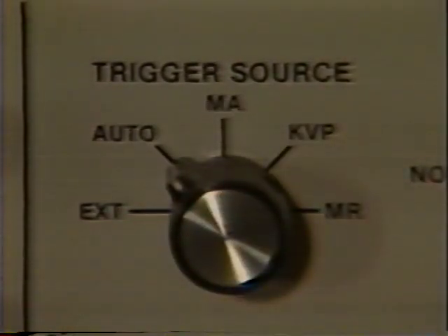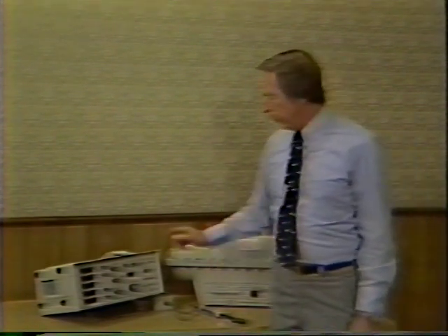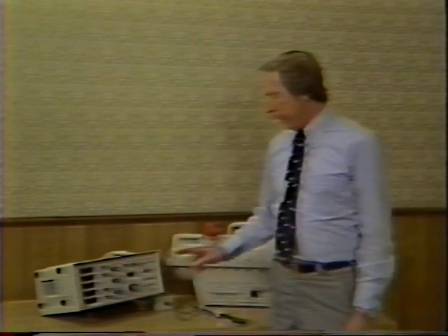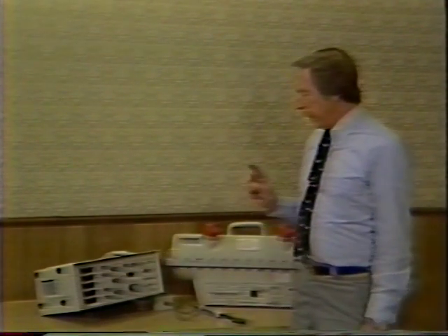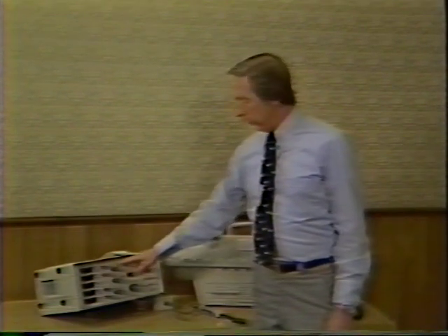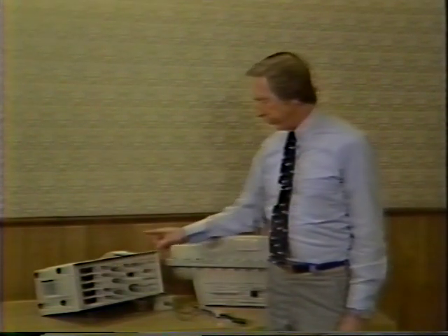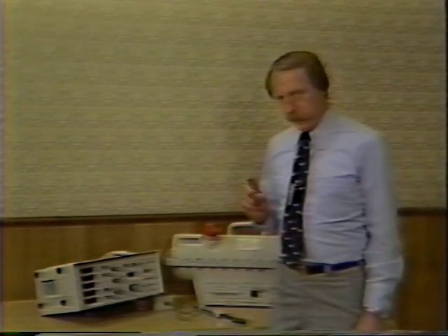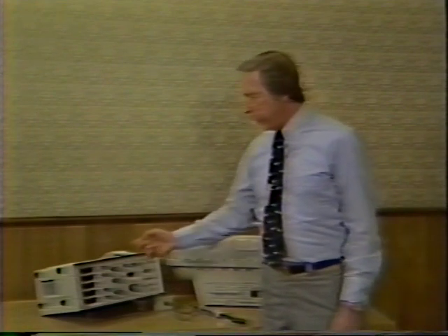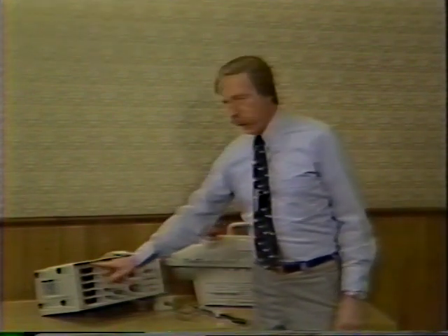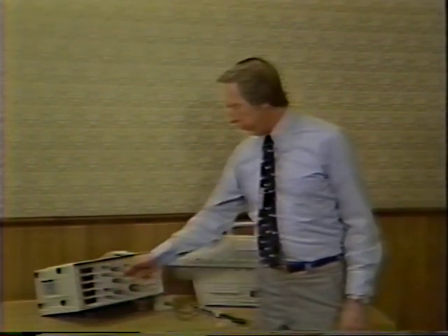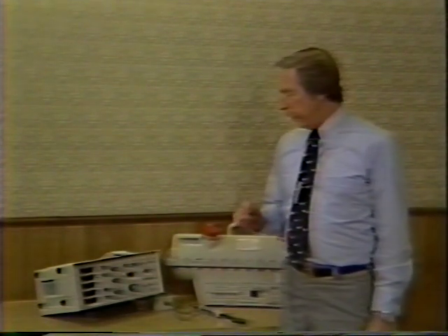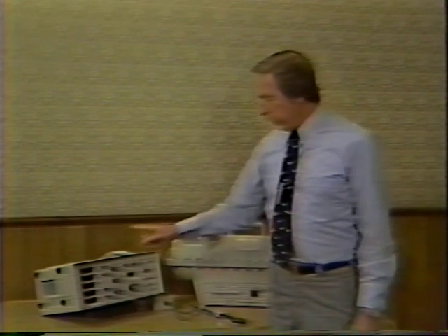One was the auto mode. Let's assume that we have the Dynalyzer in the circuit during a fluoro run. When we step on the foot switch, we trigger this unit and we take our readings. That would only be the case if we did not have the auto mode. In this mode, we're going to trigger the unit every second, such that when we press the foot switch, the unit is being triggered every second. The automatic brightness stabilizer takes over and moves kV or mA. While we're triggering every second, we will constantly have our numbers brought up to date. It's also very useful in the calibration of the filament, in that you can constantly trigger this unit in the auto mode once per second and adjust your filament current.